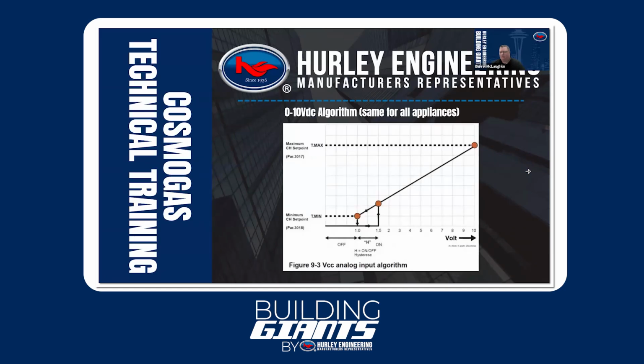Another unique feature they have when you're trying to control this remotely is you can send a 0 to 10 signal to manage set point. So you can see here, let me follow along. If I go to the max here, parameter 3017 in the control, that's where I would set my temperature at 10 volts DC power, right? Or signal. My minimum temperature, I would set in parameter 3018, and that's going to be at 1 volt.